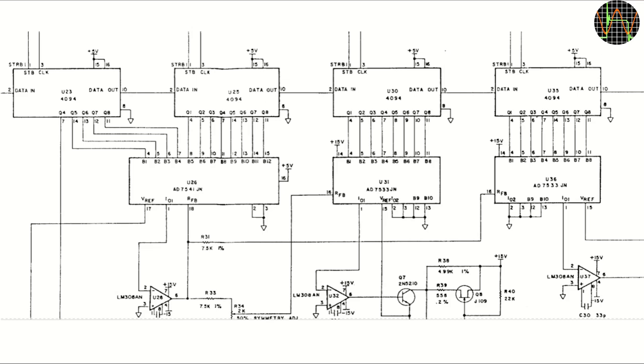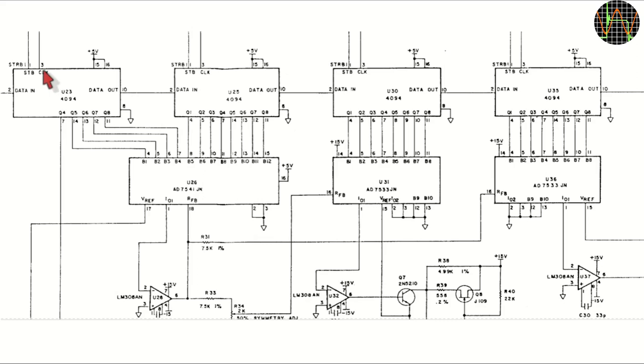I decided to investigate the digital to analog converter first. As you would expect for a system with, for the 1980s, a relatively wide frequency range, we have actually three DAC chips that control the current generator. You will recognize a familiar pattern from the first video. 4094 shift registers converting a serial data stream into parallel data on their outputs when the strobe signal is activated and these outputs provide then the digital data word to be converted into analog signals. Without going into details, I used the same method as for the offset error in part 1 by changing frequencies and looking for a change in the analog outputs.